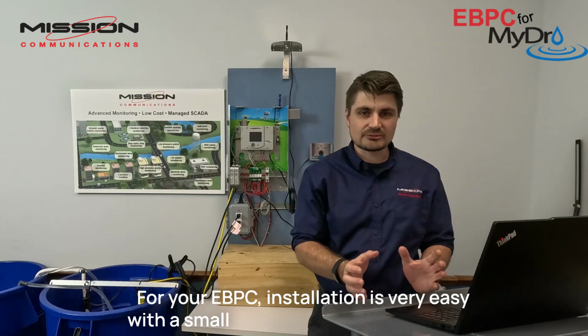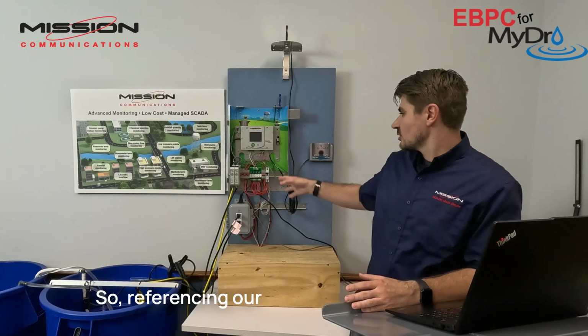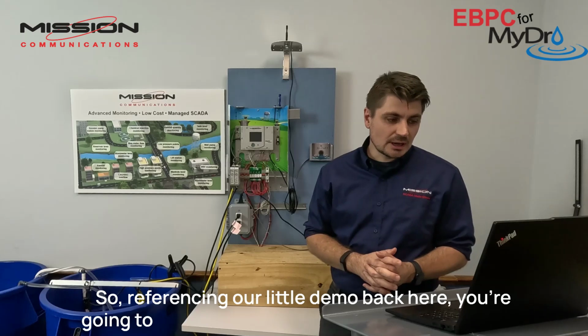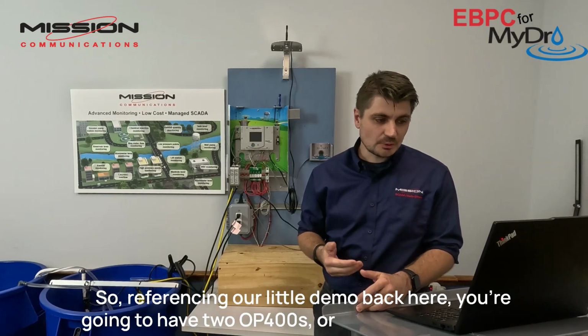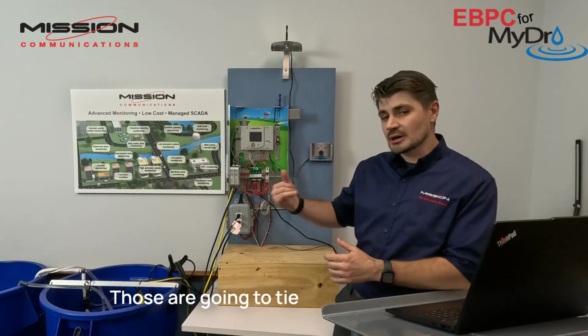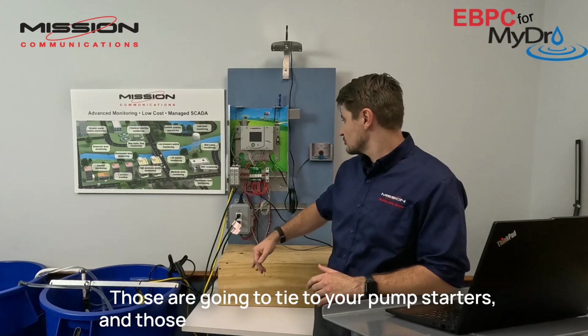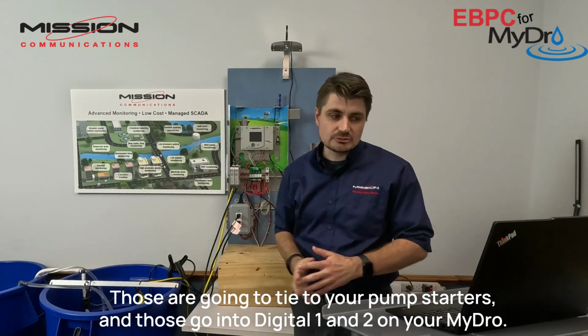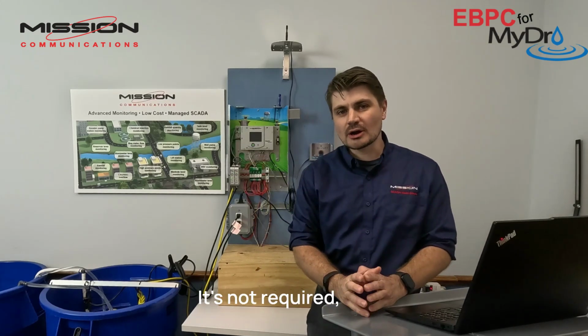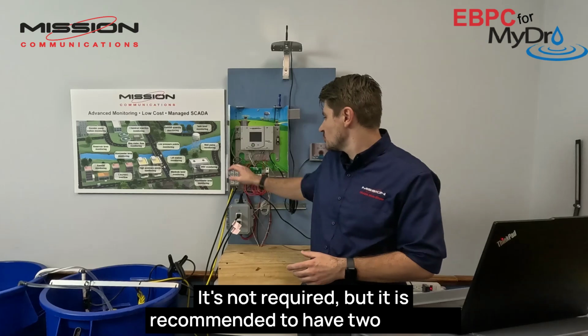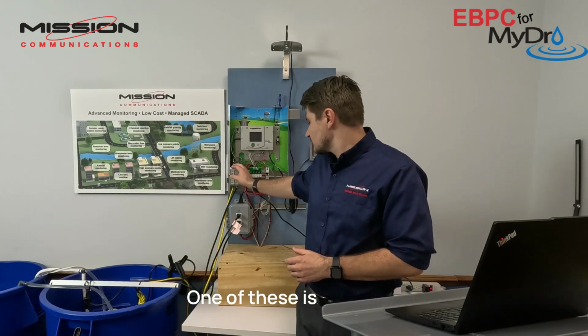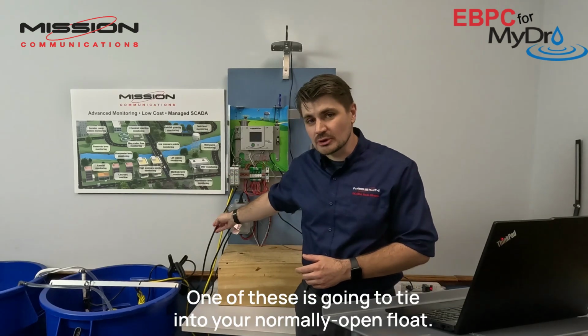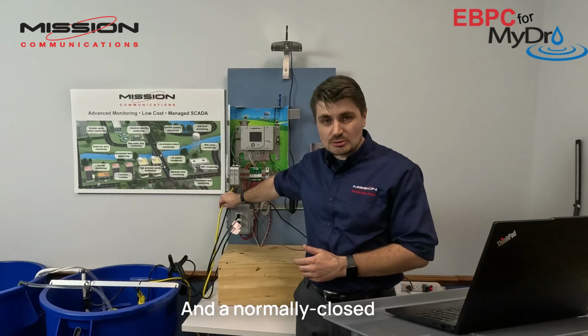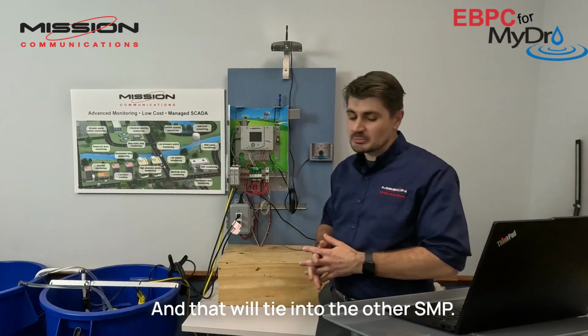For your EBPC, installation is very easy with a small amount of hardware needed to get your system up and running. So referencing our little demo back here, you're going to have 2 OP400 or our current switches. Those are going to tie to your pump starters, and those go into digital 1 and 2 on your MyDro. It's not required, but it is recommended to have 2 OP750s. One of these is going to tie into your normally open float and a normally closed float, and that will tie into the other SMP.